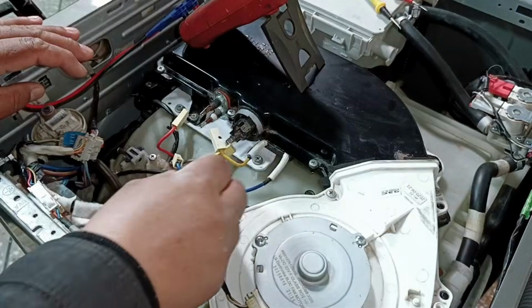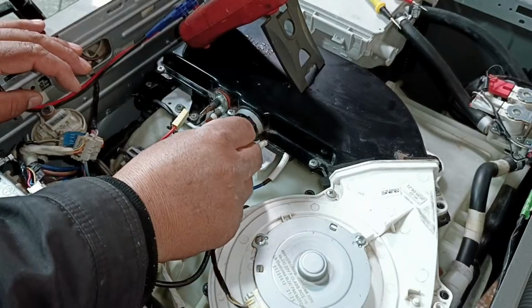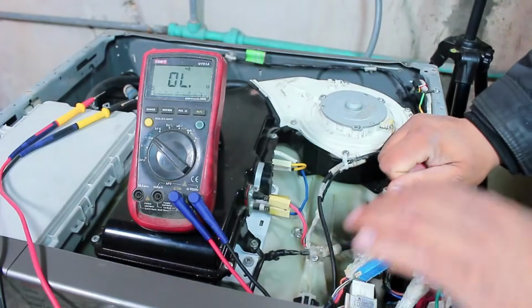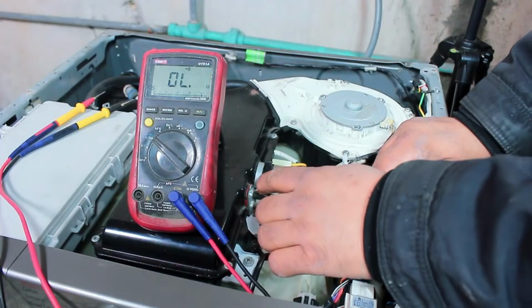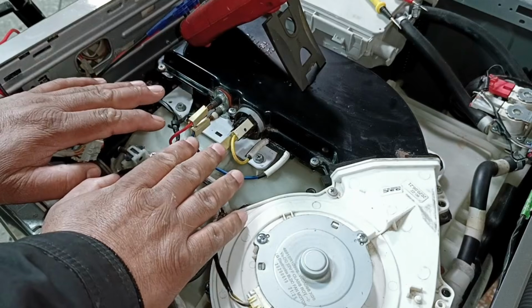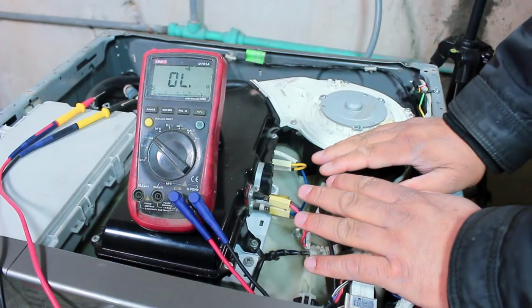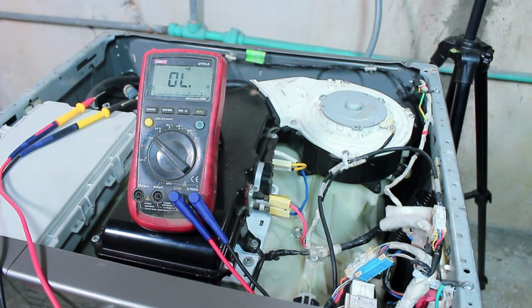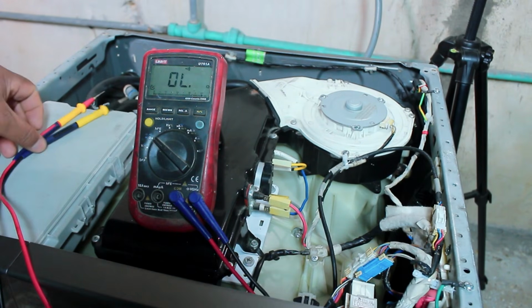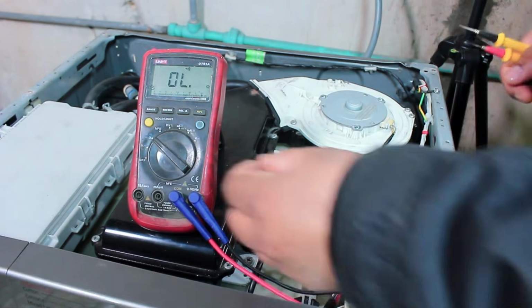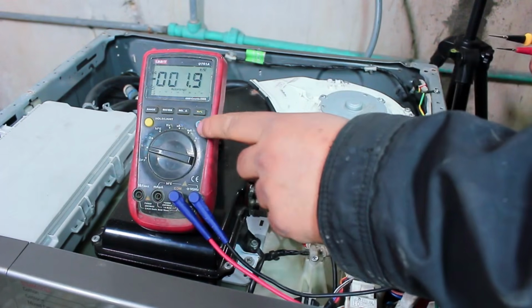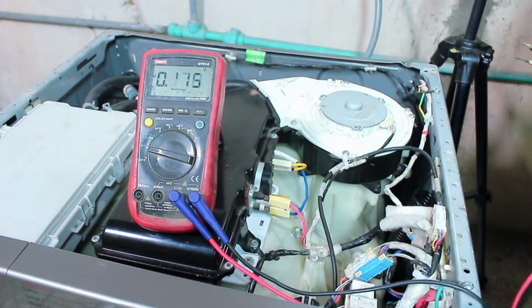For example, if we have checked all these points and the system is still not working, then the next possibility could be the main power supply. We need to check whether the main electricity is reaching this point or not. For that, first I will turn the machine on. Now the machine is switched on. I have now set the system to dry mode. For this test, we will set the multimeter to AC voltage mode. After switching it to AC mode, we will perform the test.